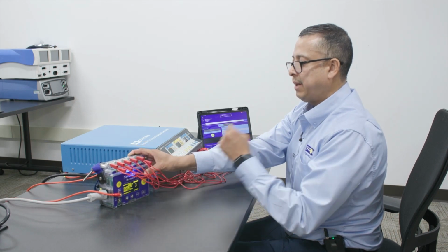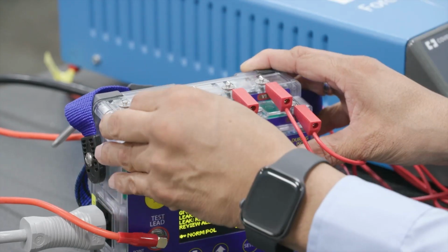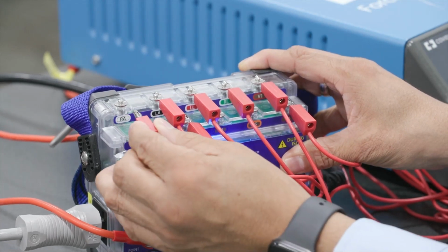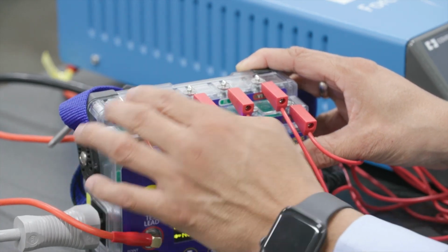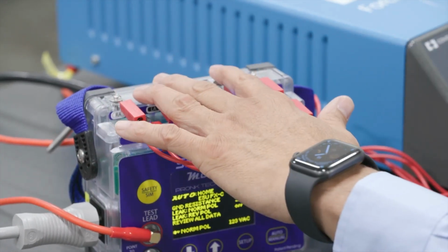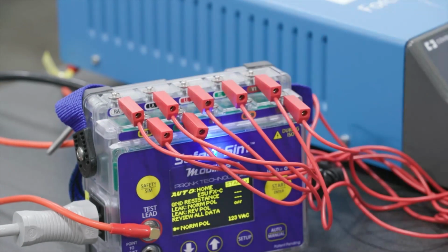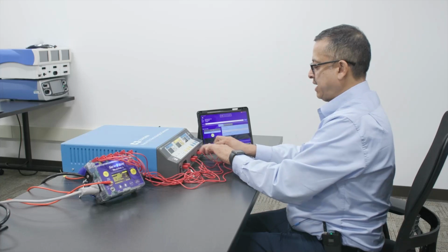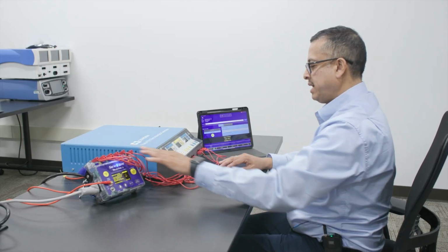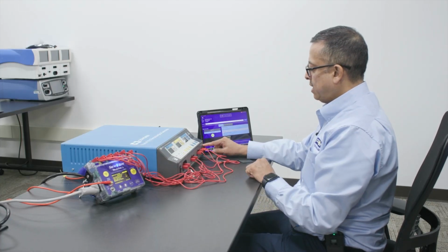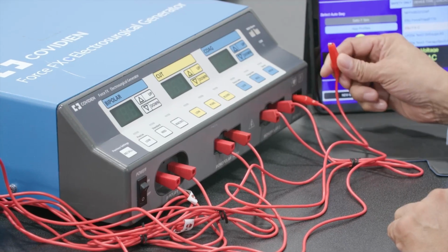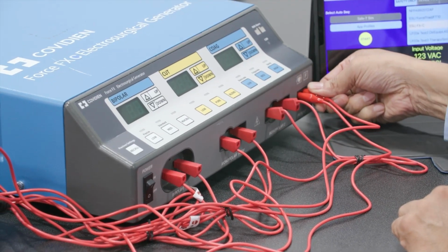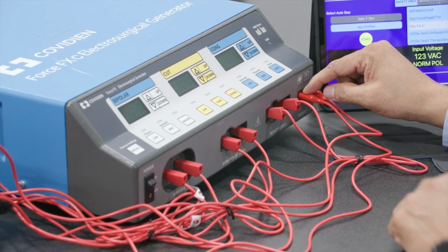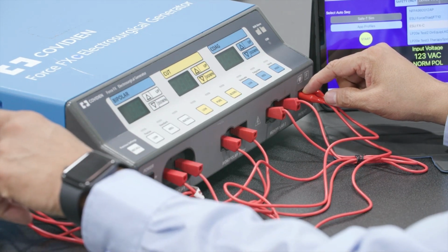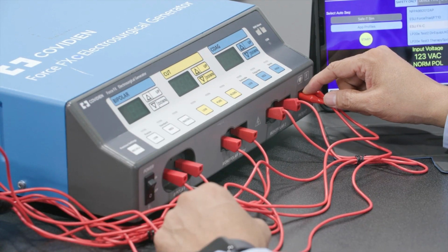They don't need to go in any particular order. You simply take the banana plug side and slide it underneath any one of the snaps to connect it to the analyzer to do our leads test. So we want to do that for each one of these ports, and you can see I've connected these already to it. And the same with the REM line. You want to use your test leads to connect to each one of those posts within the unit itself, and also connect those to any snap on the safety sim itself.